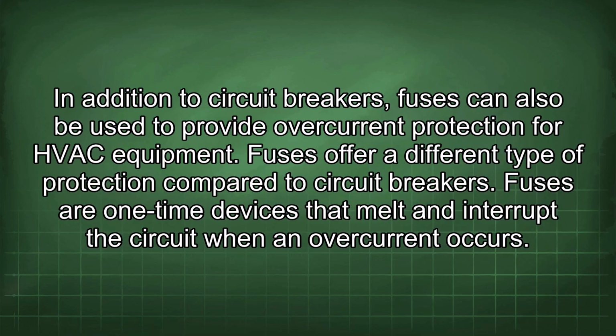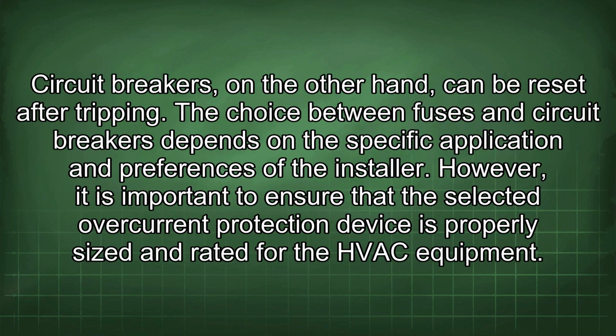In addition to circuit breakers, fuses can also be used to provide overcurrent protection for HVAC equipment. Fuses offer a different type of protection compared to circuit breakers. Fuses are one-time devices that melt and interrupt the circuit when an overcurrent occurs. Circuit breakers, on the other hand, can be reset after tripping. The choice between fuses and circuit breakers depends on the specific application and preferences of the installer. However, it is important to ensure that the selected overcurrent protection device is properly sized and rated for the HVAC equipment.